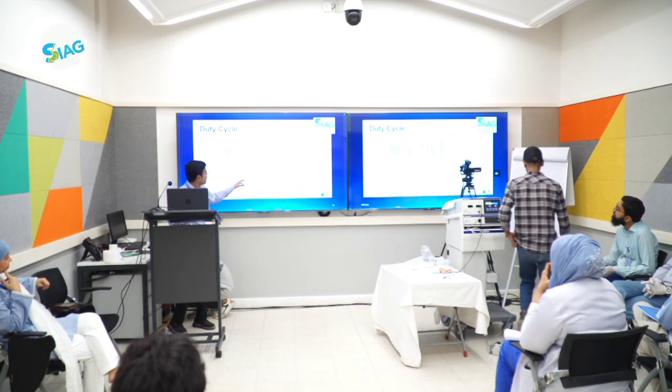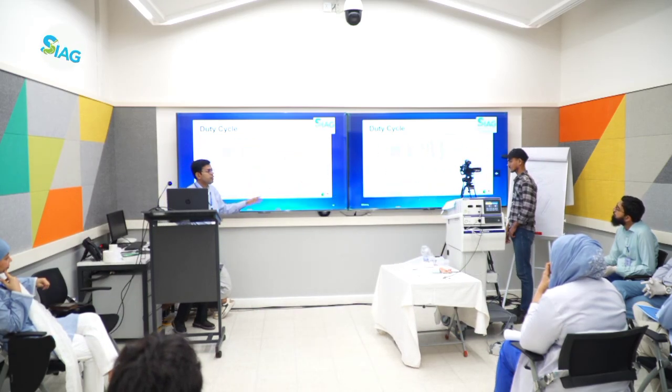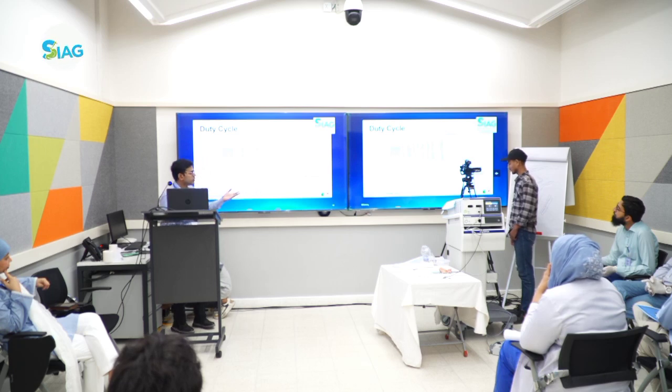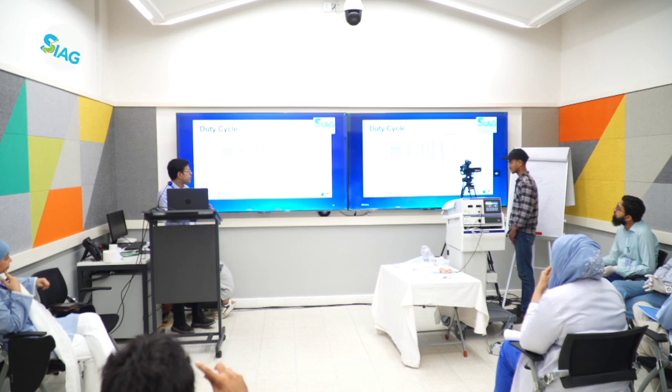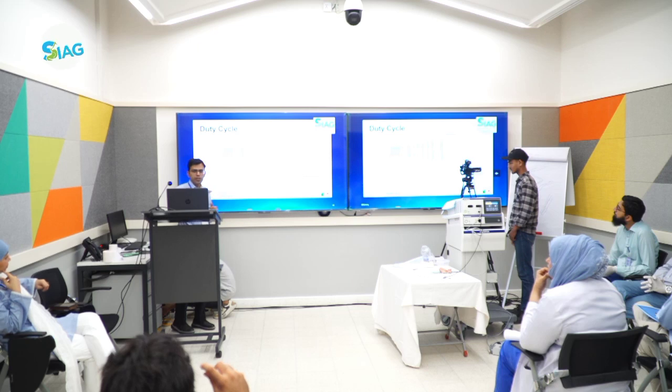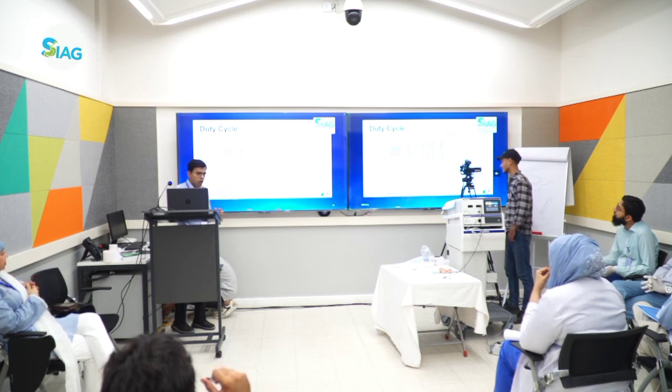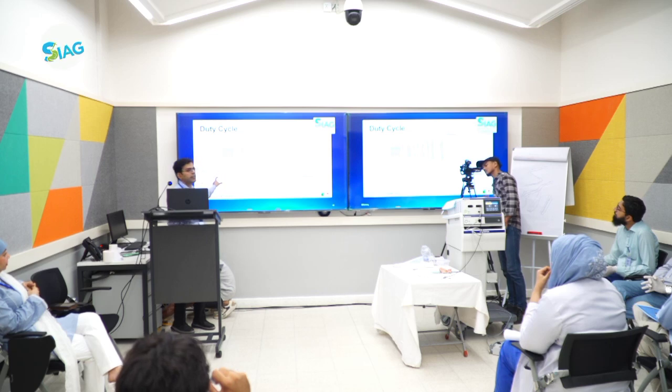In between, we have blend 1, blend 2, blend 3. You always see them on the machine, but we are unable to appreciate what they actually mean. So if we talk about blend 1, there is flow of current during 50% of the cycle. In blend 2, it's 40% of the cycle. And in blend 3, it's just 25%. So the longer the current flows, the more the cutting technique.